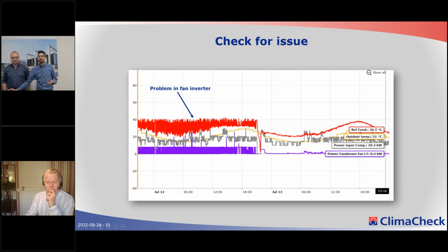And before, when the issue was happening, we're looking at a very unstable situation because the fans basically are turning on and off all the time, maximum power and then back to zero, maximum power and then back to zero. This is what our partner could figure out with the contractor, that they most probably had an issue with the fans, and in this case it was an issue with the inverters, where they could check that the controls were not set up properly.